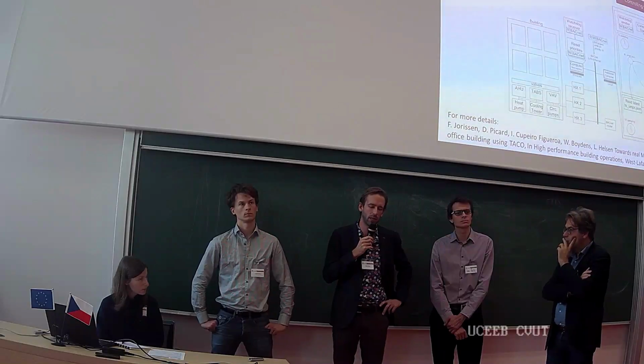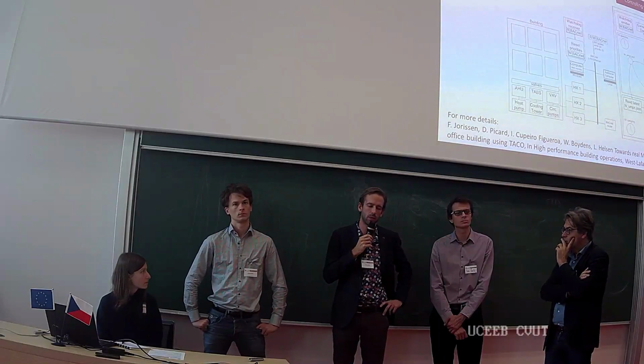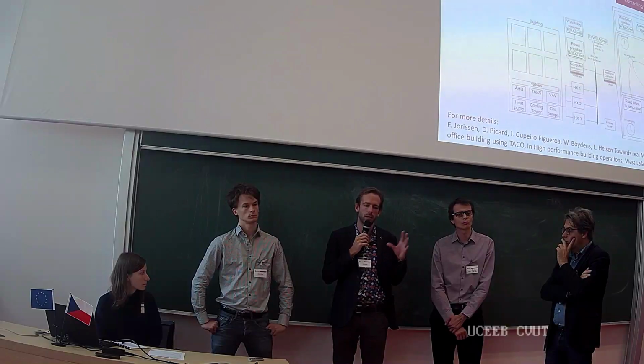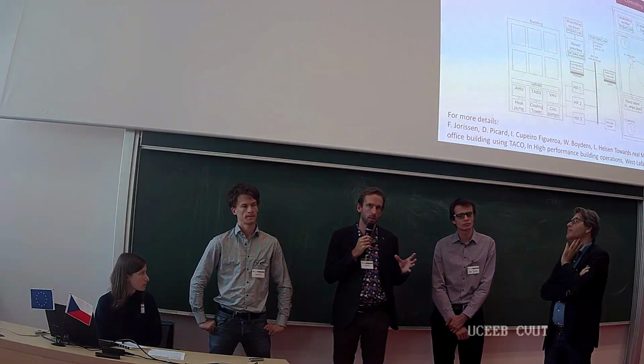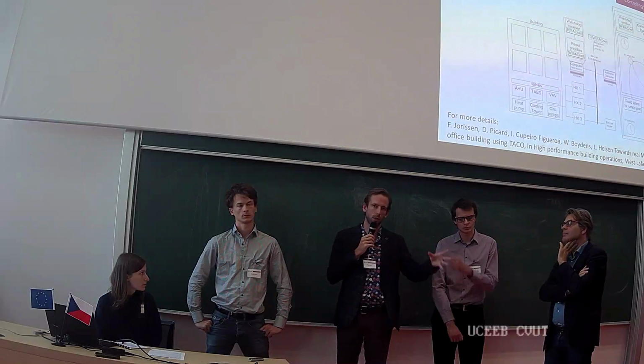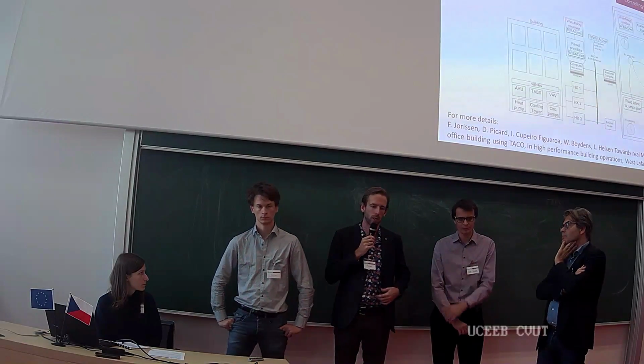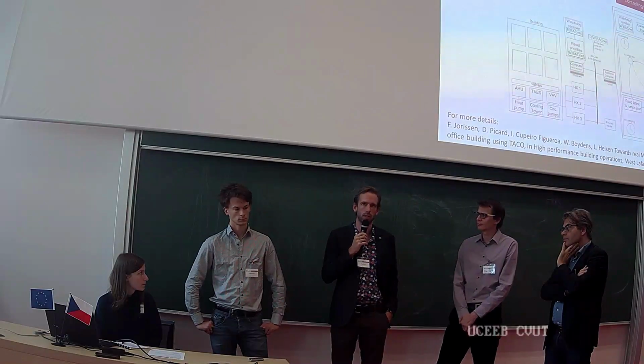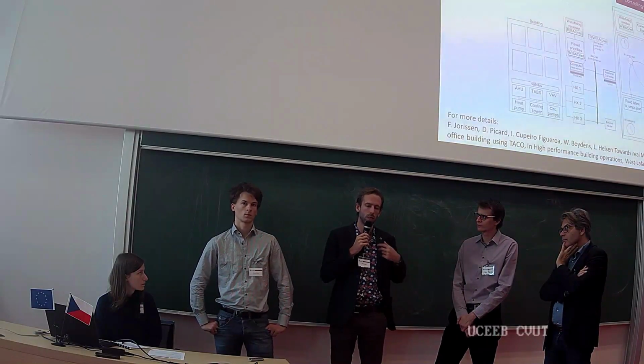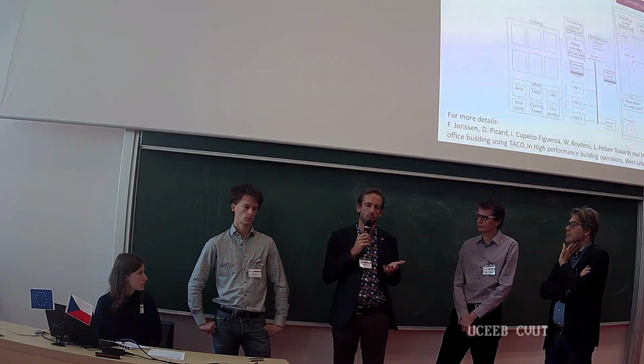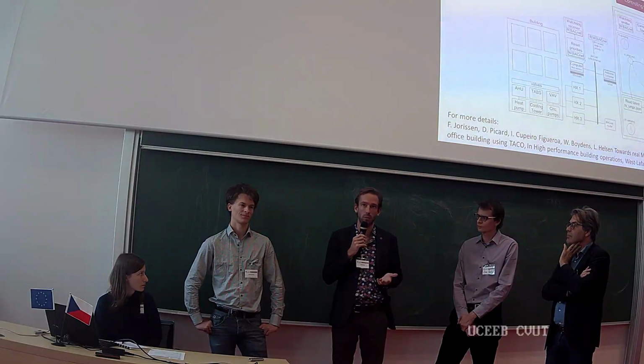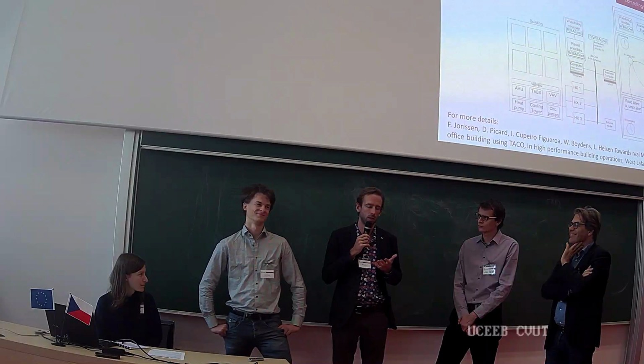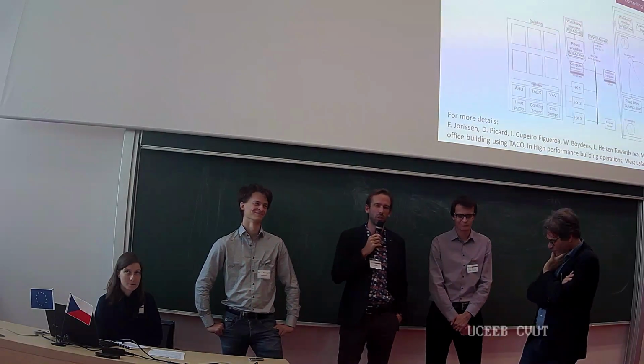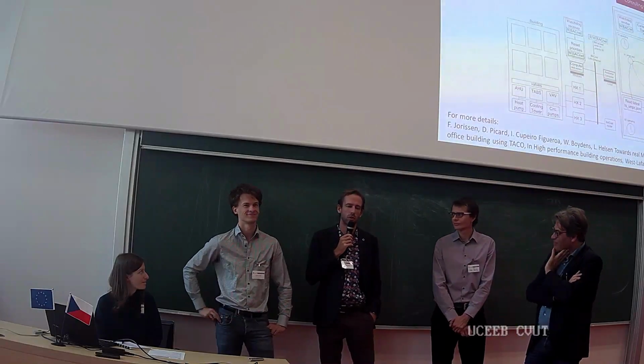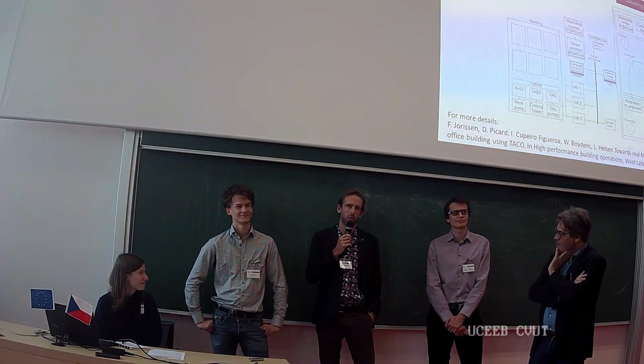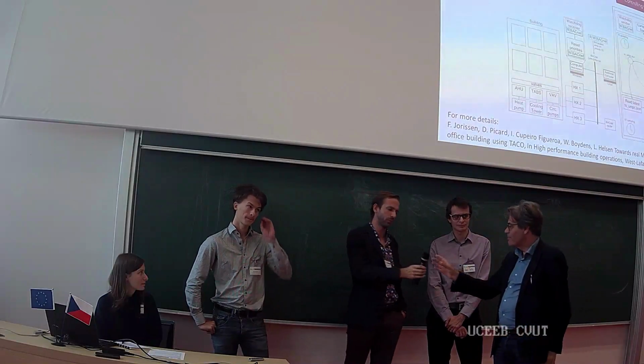One final thing I'd like to add is that typically the system we're controlling, the building, is a continuous system. You've got disturbances that are completely continuous, people going in and out, heat flow rates. So it makes sense to control it as a continuous system also. For me, I'd turn it around and say: guys, stop using on-off pumps, stop using on-off heat pumps. It's a bad idea, stop doing it, seriously. In the longer run, I think we won't have this issue anymore, and we can gain a lot from using frequency control instead.